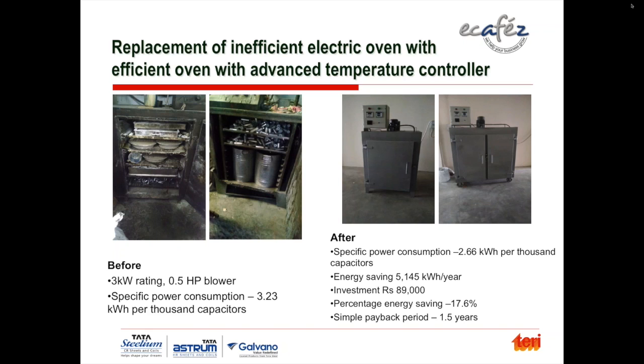After installation, the specific energy consumption came down to 2.66 kilowatt hour per thousand. To give you a magnitude of the energy saving, it saved 5,145 units of electricity per year. The payback on the investment of 89,000 was achieved within 1.5 years. So after the energy audit, they installed this more efficient furnace and got a very good energy saving.